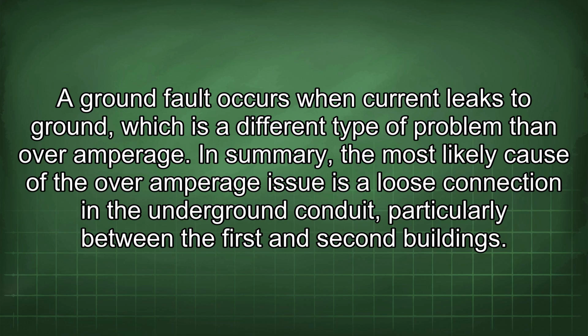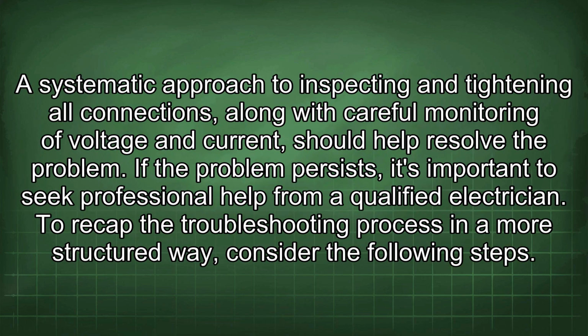In summary, the most likely cause of the over-amperage issue is a loose connection in the underground conduit, particularly between the first and second buildings. A systematic approach to inspecting and tightening all connections, along with careful monitoring of voltage and current, should help resolve the problem. If the problem persists, it's important to seek professional help from a qualified electrician. To recap the troubleshooting process in a more structured way, consider the following steps.